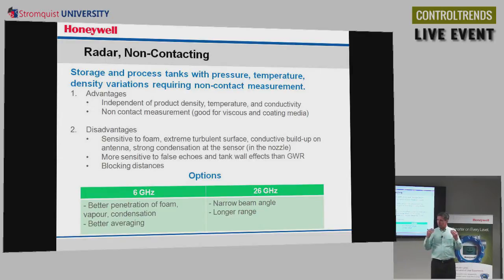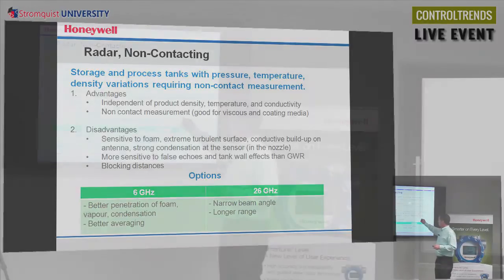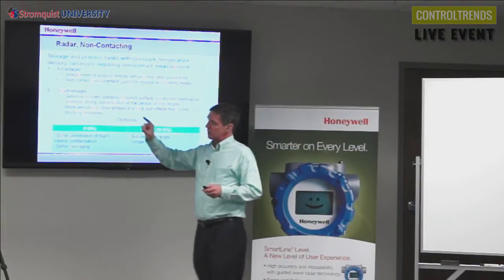This morning we talked about how we want to send the pulse right down the waveguide, and we want it to reflect right back up. Well, we've got that waveguide to guide it normally with our guided wave radar, but with the non-contacting, the wave is going to tend to go out to the side. We want it to be as focused as possible, but inevitably it's going to go off to the side. It may bounce off the tank wall, from the tank wall go off the surface and come back up again. We'll get multiple reflections, and these multiple reflections can be a problem when it comes to determining what is actually the surface reflection. And it has the same issues with blocking distance at the top and the bottom.